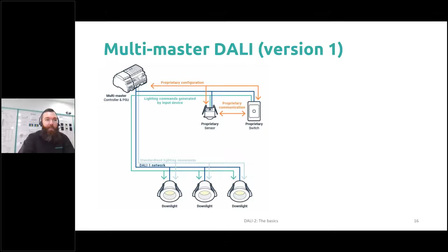Now, the big thing is that we've actually made these devices much simpler. So instead of having an input device sending a lighting command back out to our devices directly, these things now just send what we call an event message. An event message is a very simple string of commands which introduces who the sensor is and what information it has to tell the world. So if we go back to that same example where someone's walking into a room, that sensor is going to generate this event message, and it will say, hi, I am sensor at address 4. I have detected occupancy, okay?